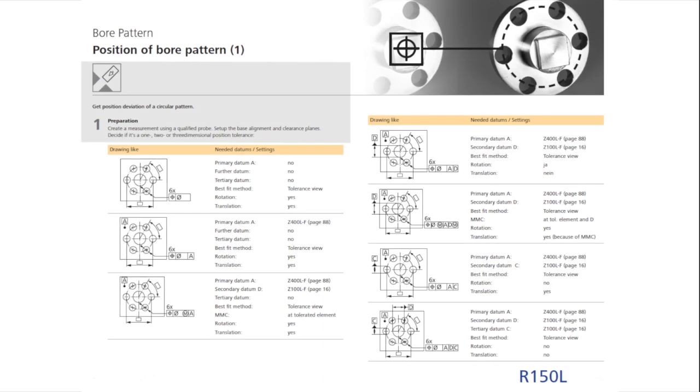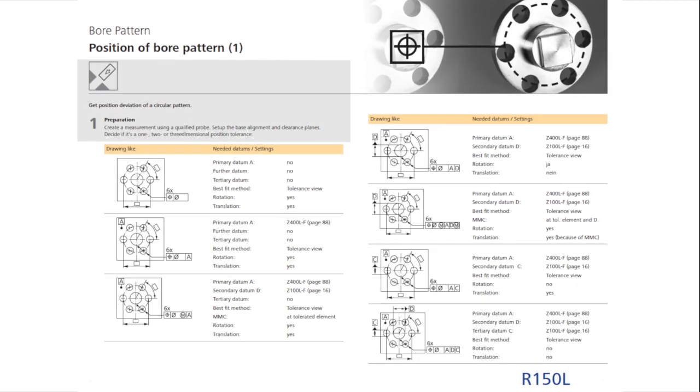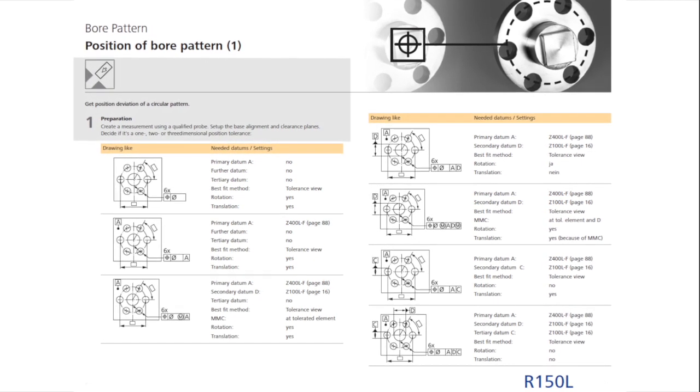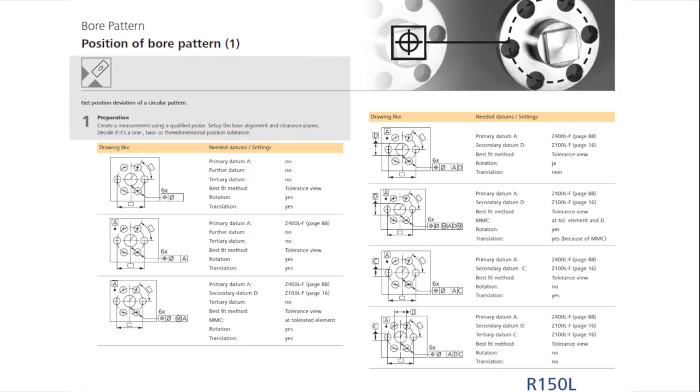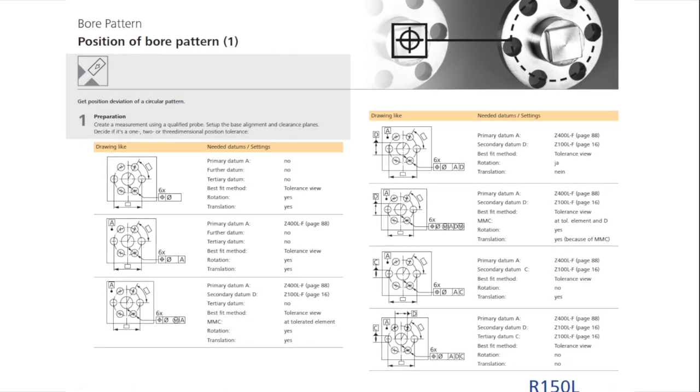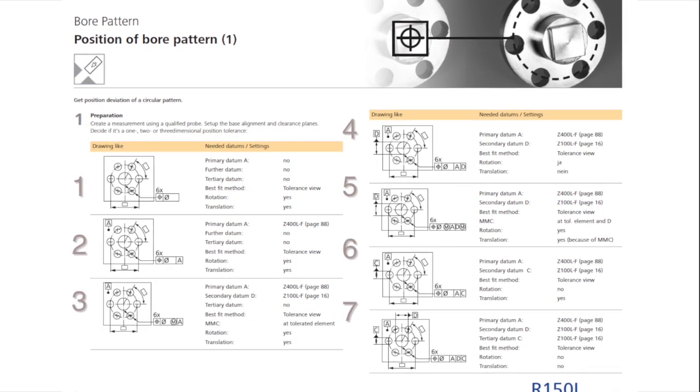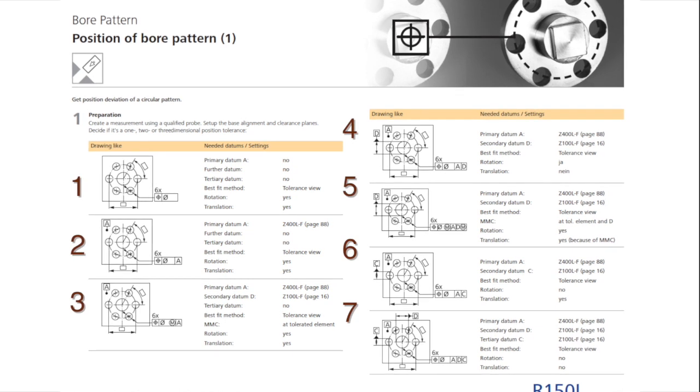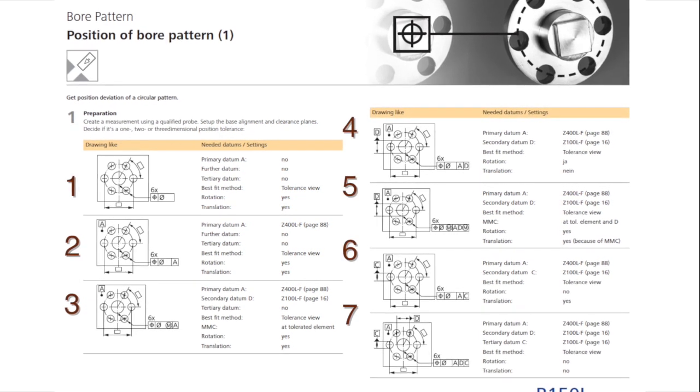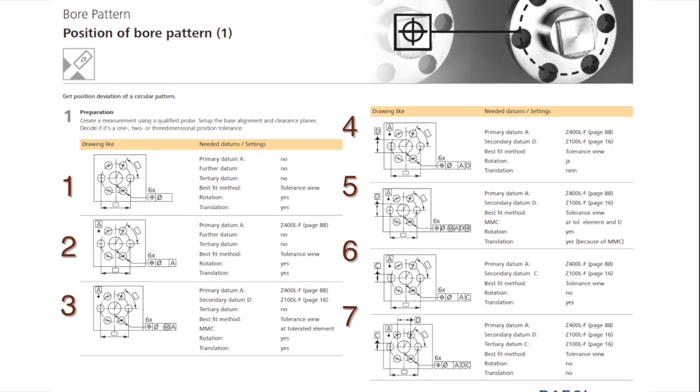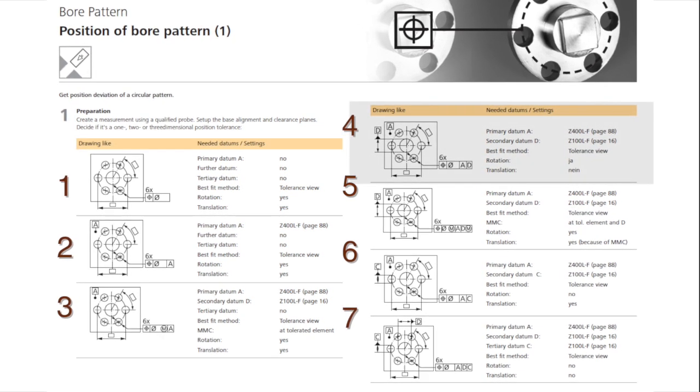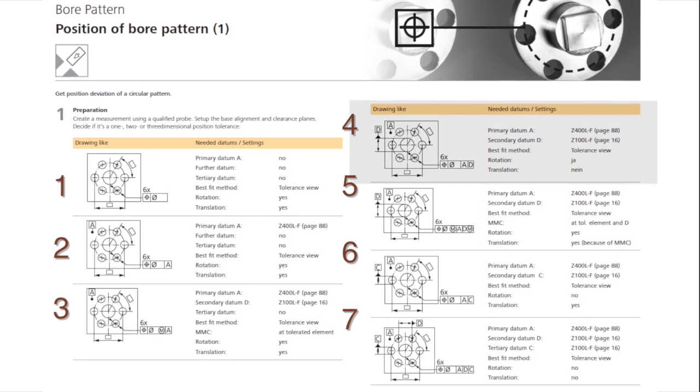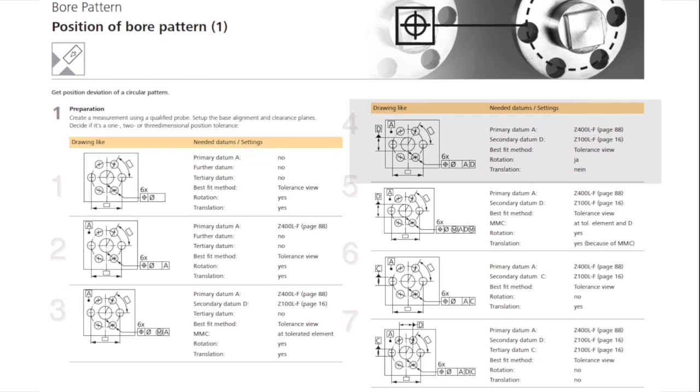Step 1, again, is to prepare for the measurement by qualifying the probe systems, aligning the workpiece, and building clearance planes for navigation. In addition, different possibilities for the datum or reference frame construction can be seen in the table. For this example, case 4 matches the print requirement, with datums A and D.